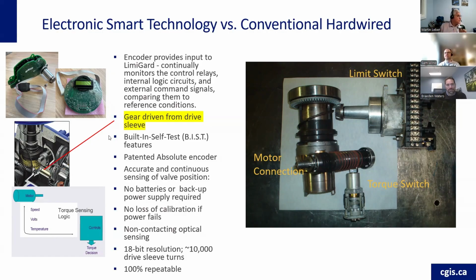This bevel gear you see right here is really the only interface to the controls. You have your switches here. This arrangement simulates your encoders, but it also feeds the logic that compares the motor speed, voltage, and temperature, and comes up with a torque decision, which models the torque switch on this side. So torque sensing is software based in the electronic actuator.